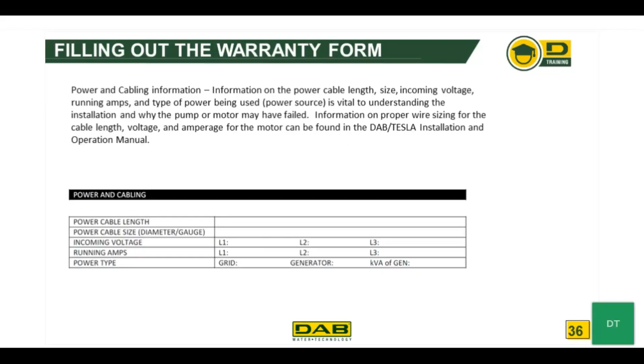This is the power and cabling information. Power and cabling information is very important to determining whether a proper installation was made or whether there might have been a problem with that installation. Information on the cable length, the size, incoming voltage, running amps, and the type of power being used, what kind of power source you're using, such as a generator or power from the grid, is vital to understanding the installation and why the pump and motor may have failed. Information on the proper wire sizing for the cable length, voltage, and amperage for the motor can be found in the DAB Tesla installation and operation manual, which you can get from DAB and Tesla.